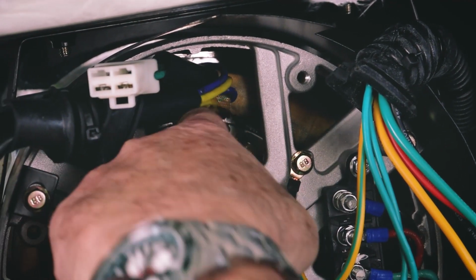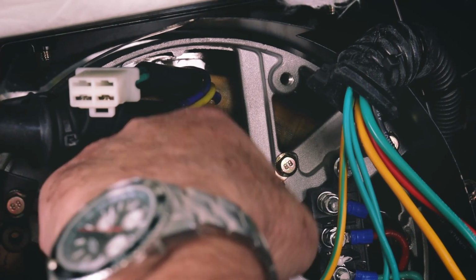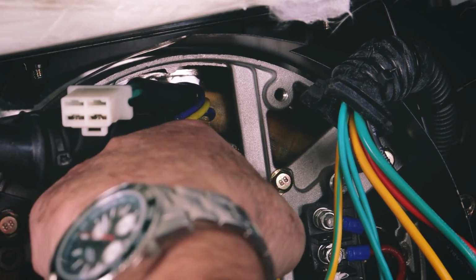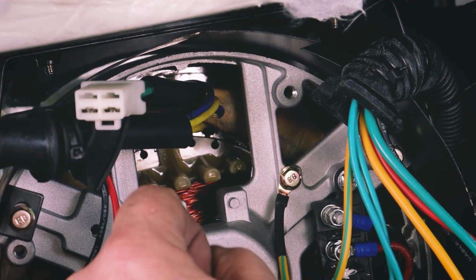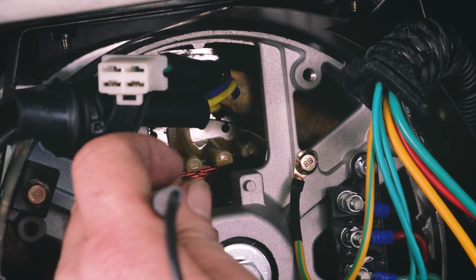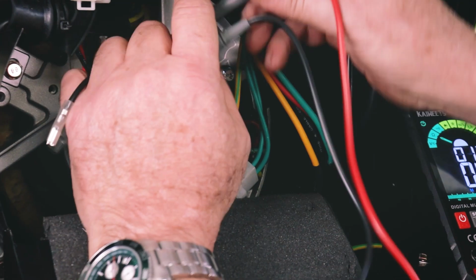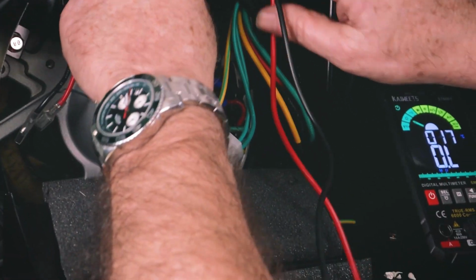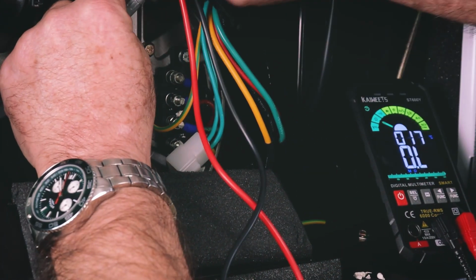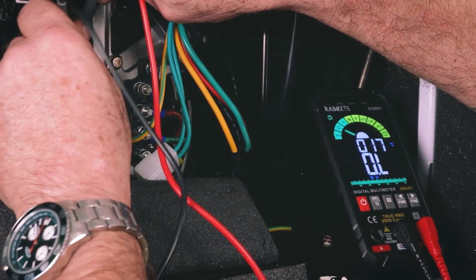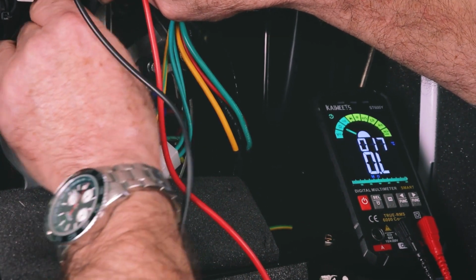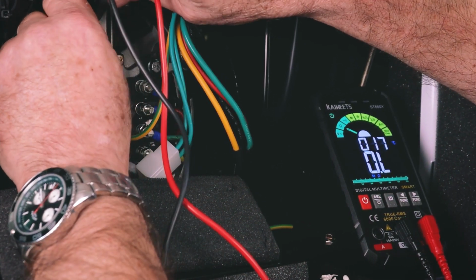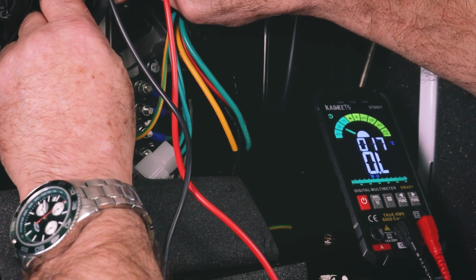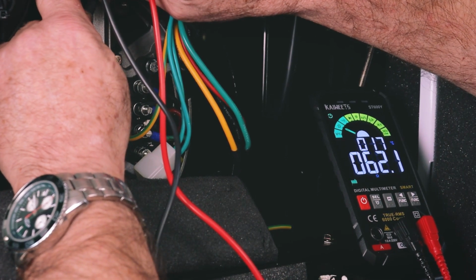So those rings are down in here. Now, I can physically see them if I stick my head over the top, but there's no way we'll get the camera in. So what I need to do is check resistance in ohms across these 2 rings. So it's going to be tricky for me. I can't really show you what I'm doing here because I won't be able to let you get in there. I normally use my long probes for this, and I've got some 90-degree ones as well. So let's see if I can get in there.